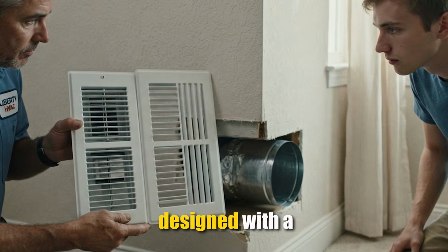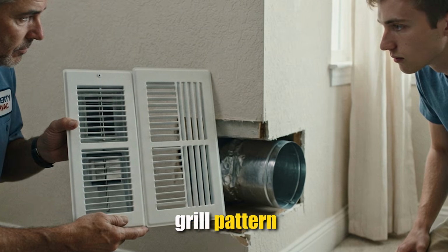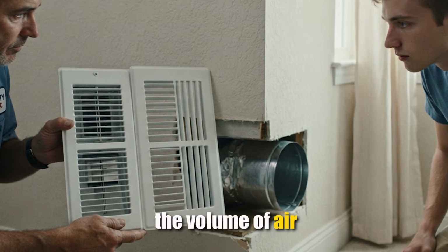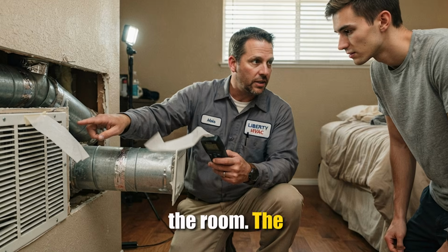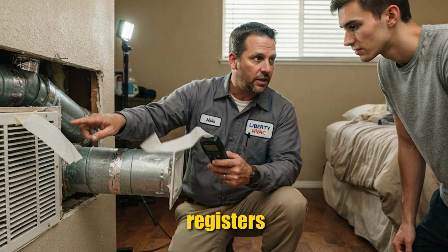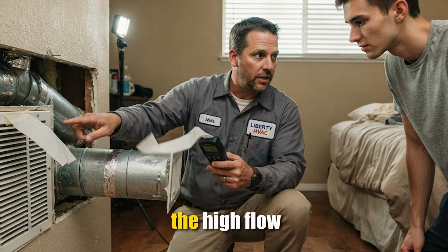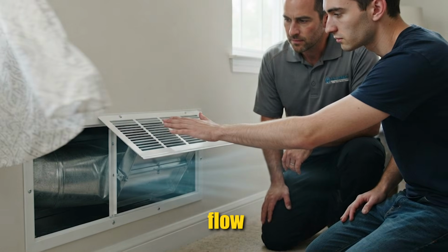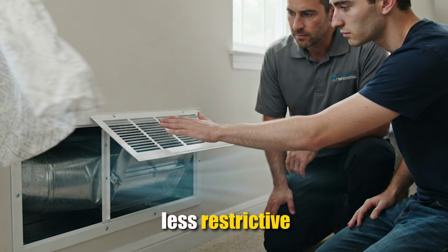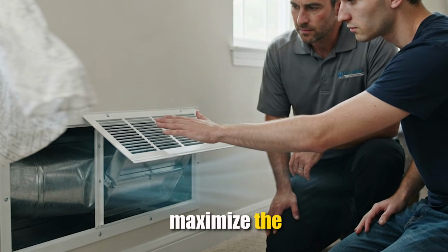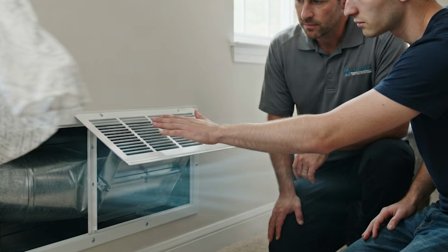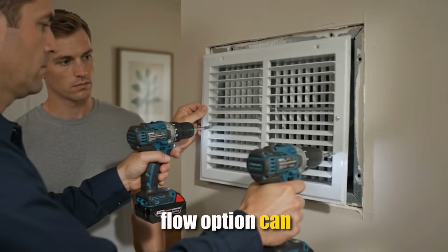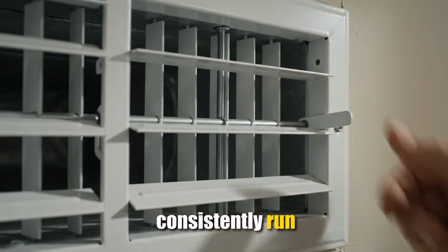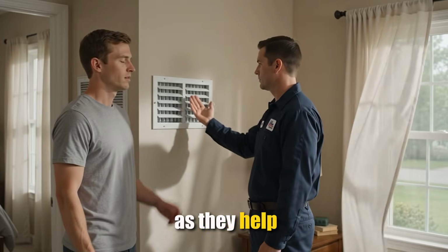High-flow registers are designed with a less restrictive grill pattern that maximizes the volume of air delivered into the room. The same duct pressure behind both registers produces more airflow out of the high-flow version. Selecting a high-flow option can be beneficial in rooms that consistently run too hot or cold, as they help increase the cubic feet per minute of air output.